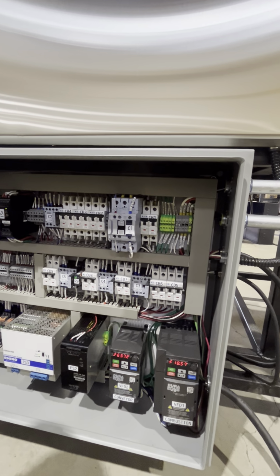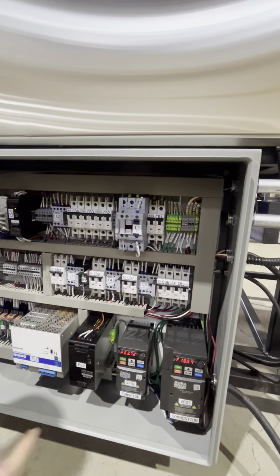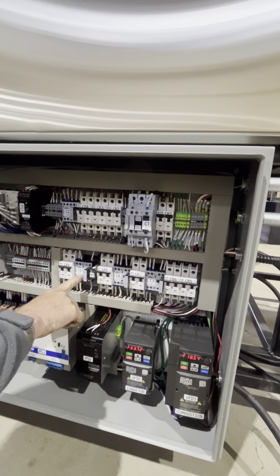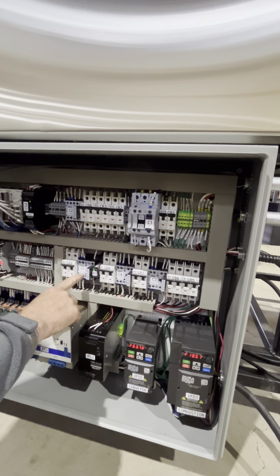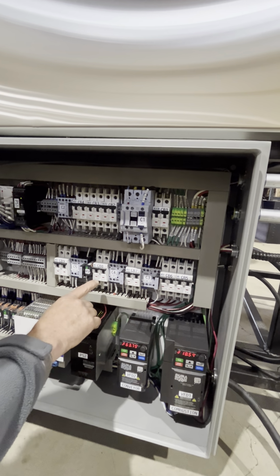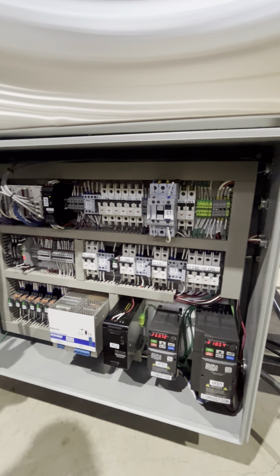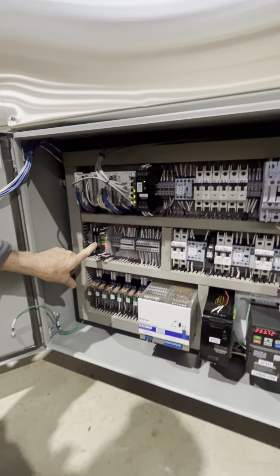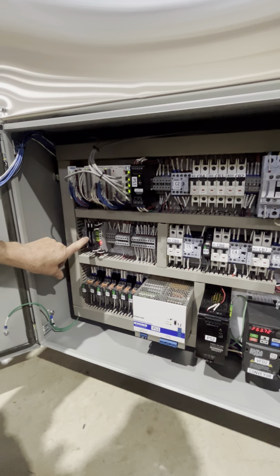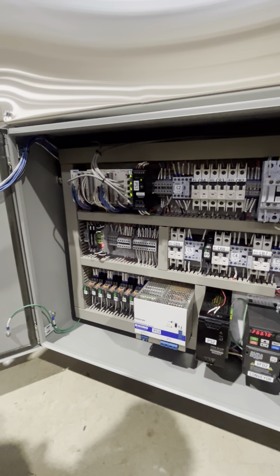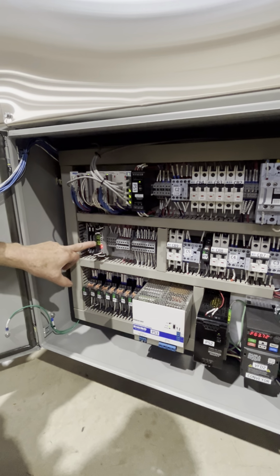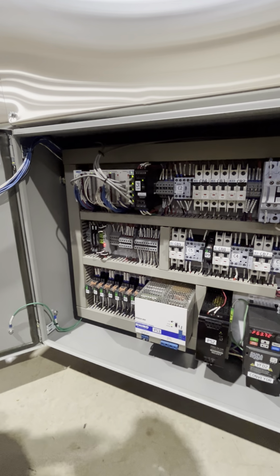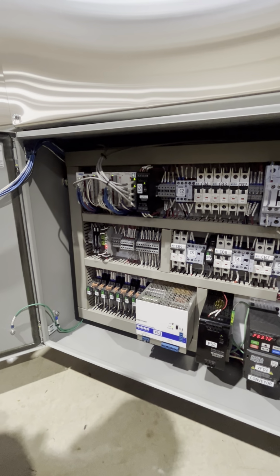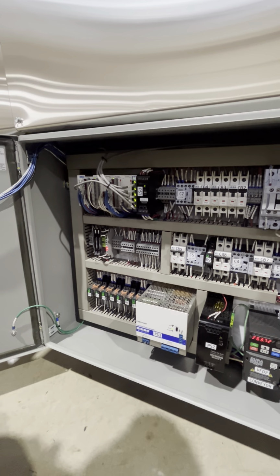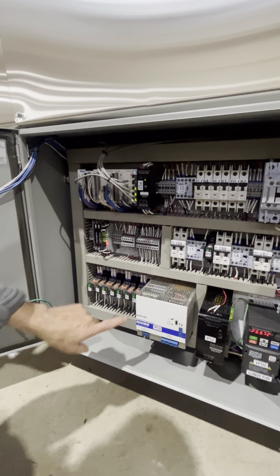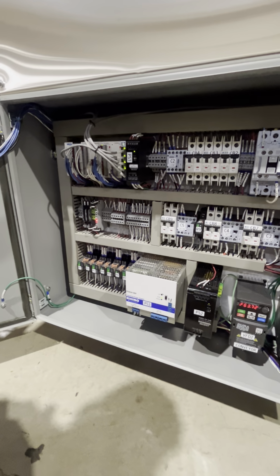So if you do have a function that's not working properly, the first thing to do would be to look at, for instance, if the igniters aren't igniting, there's a relay for the igniter, and there's a circuit breaker for the igniter. On this side over here, these two are the fuses for the HMI. So each HMI has got its own individual fuse. So anytime you power up and one of the HMIs isn't working, the first thing to look at would be the fuse itself.